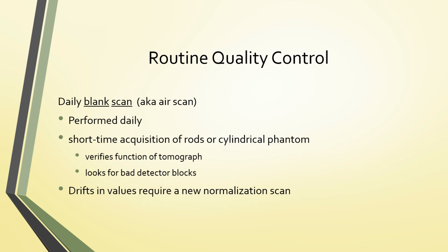Now for the routine quality control, every day a blank scan is performed. This is sometimes also known as an air scan, but this is a short time acquisition of the rods or a cylindrical phantom, and it verifies the function of the tomographic instrument of the PET scanner, and really it's looking for bad detector blocks. Remember, with our daily QC, we want to know, is it okay to scan today?